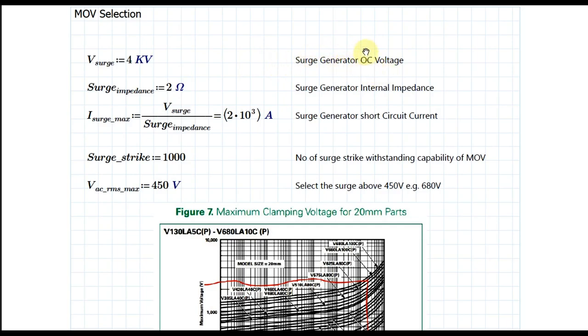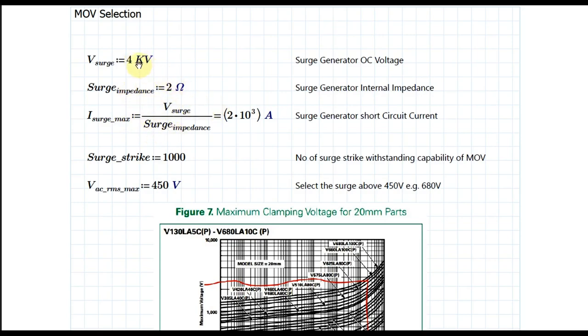If you look at the standard, you can find the impedance of the surge generator. The surge generator internal impedance equals 2 ohms. Now you have to find the surge generator short-circuit current: I_surge_max = V_surge / Z_surge = 4 kV / 2 Ω = 2 kilo-amperes, or 2000 amperes.